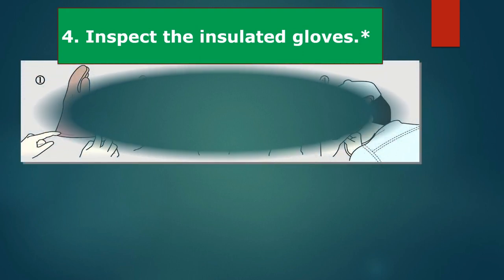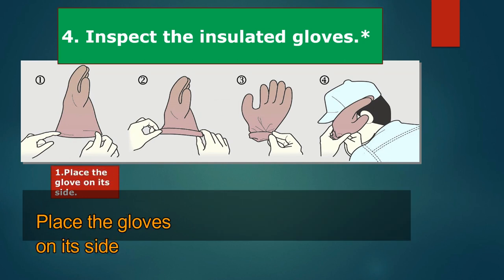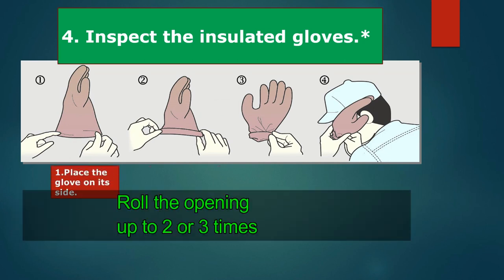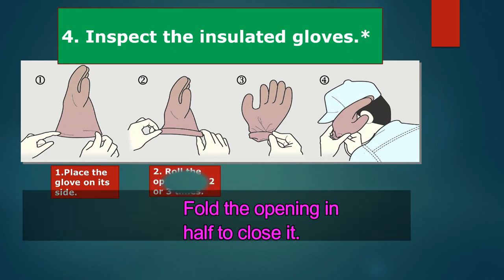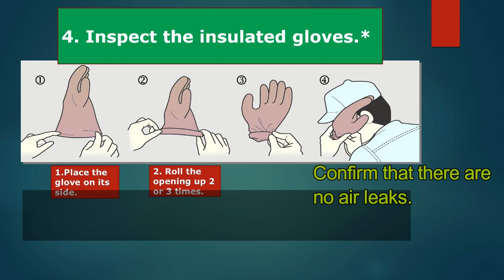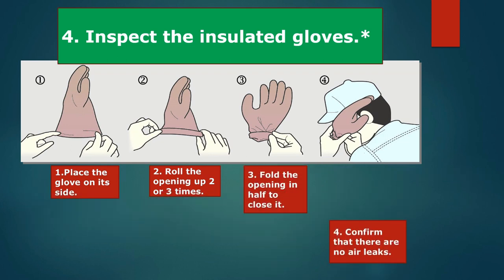Before using insulated gloves, be sure to check them for cracks, tears and other types of damage by performing the following procedure. Place the glove on its side. Roll the opening up 2 or 3 times. Fold the opening in half to close it. Confirm that there are no air leaks. Do not wear wet insulated gloves. This may lead to electrocution.